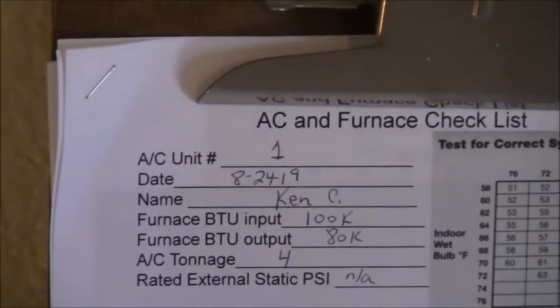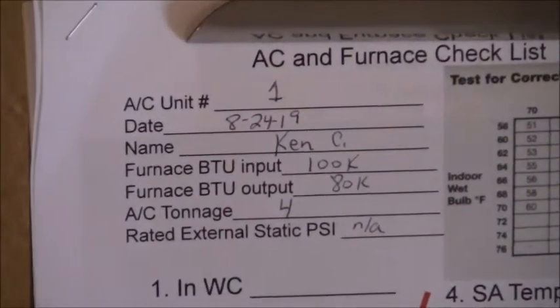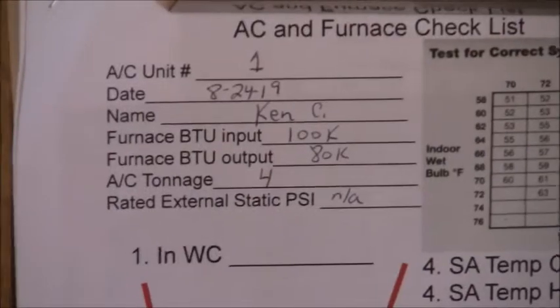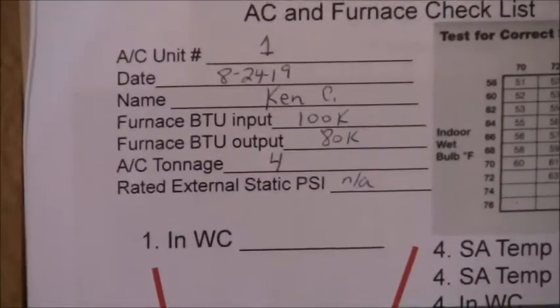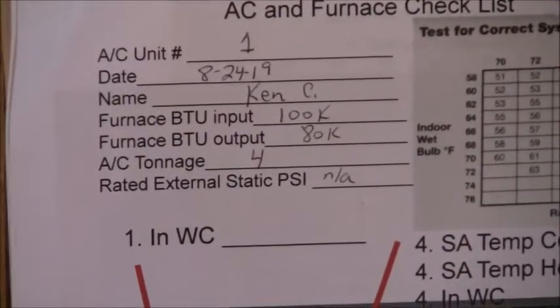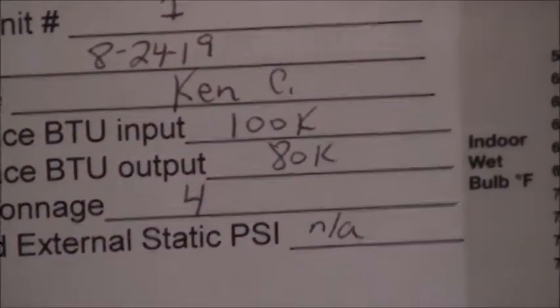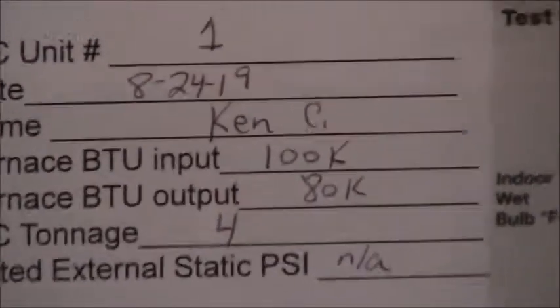Okay, so we're also going to be filling out our checklist to check the system out and see how it's going. So the first thing I want to do is go to the thermostat downstairs and put the thermostat in heating so that I can see the fan. Now the natural gas valve is shut off, so the flame isn't going to come on, so the furnace isn't going to start producing heat. Alright, so I started filling this out with the unit number, the date, my name, what the furnace input is, what the furnace output is, the AC tonnage, which is 4 tons, and the rated external static pressure. And I put down NA because we don't know what it is, because it's not labeled on the data nameplate.